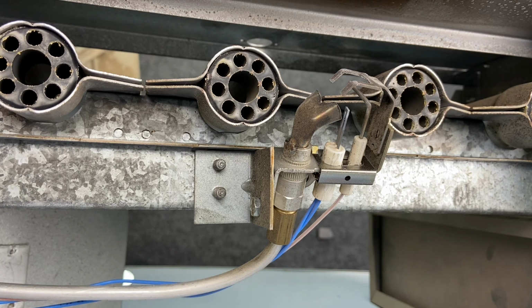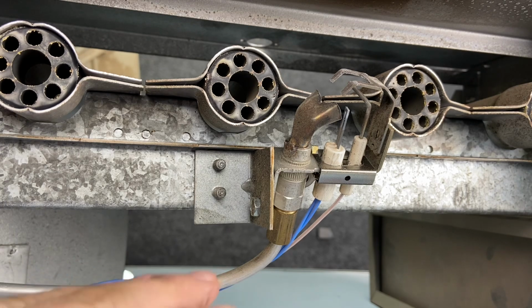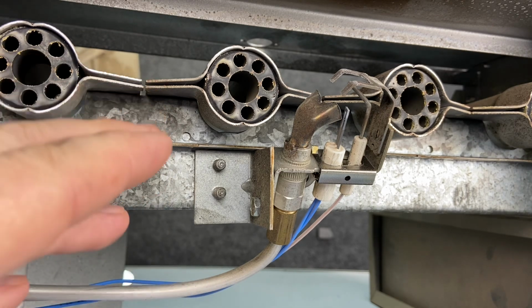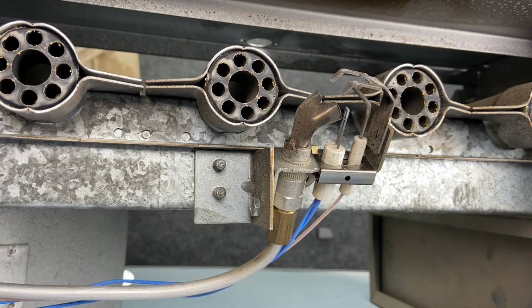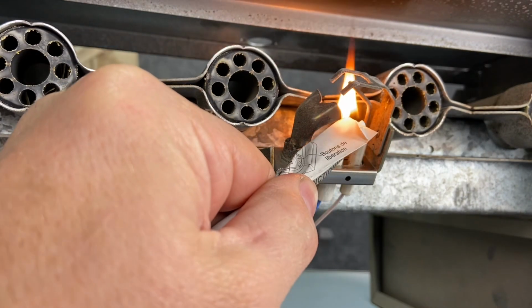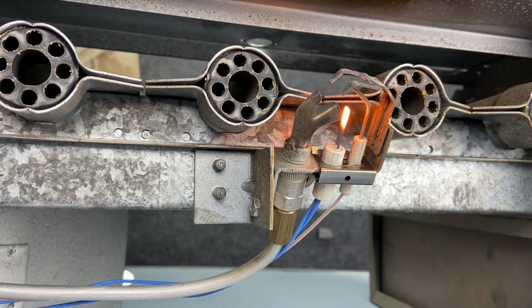So we're going to plug this furnace in. I got it wired up to where we can see the hot surface igniter happen. Now I can't have it to where the pilot lights, because if the pilot lights, then the main burners would light right afterwards, and that would burn up the camera, and I would be in a little bit of trouble. So we're going to go through a sequence of operation, have the thermostat call for heat, connect R to W. Inducer fan runs, pulls the vacuum to the pressure switch. Now we can see that hot surface igniter getting hot. It's turning bright red, and it gets so hot that we should be able to touch a piece of paper to that, and it just instantly catches on fire. So it is a hot surface igniter.